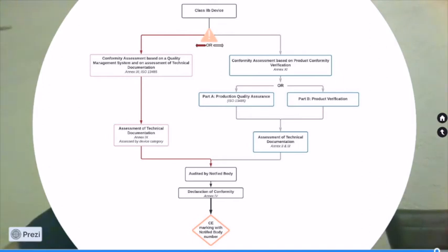The next step will be the conformity assessment and technical documentation. However, important parts of the technical documentation, as for example the general safety and the performance requirements, need more elaboration. And other parts, such as the preclinical and clinical data, are even missing. And also for the conformity assessment, we need a final and complete product. And when looking at the current state of the device, data and information is still being collected and optimized. So currently we're not ready to do these assessments, and that's why we have decided to put the medical device at this stage in the flowchart.